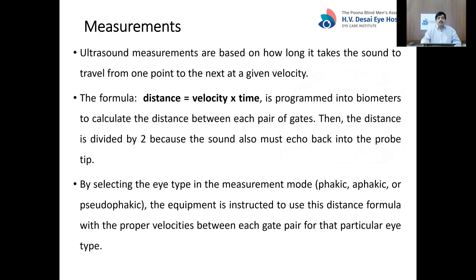Ultrasonic measurements are based on how long the sound takes to travel from one point to the next at a given velocity. The formula used is: distance equals velocity multiplied by time. This is programmed into the biometer to calculate the distance between the various gates. The distance is then divided by two because the sound wave must travel to the interface and come back to the tip.